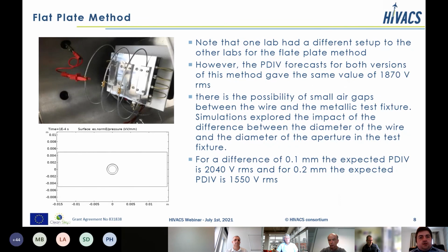So one of the labs had a slightly different test setup for the flat plate. So the geometry was considered in the models in this case. For the other labs, we estimate that the PDIV for the flat plate method is 1870 volts RMS. But with this specialized test setup, there's also the possibility of small air gaps. Now, we don't know exactly what the size of those air gaps is, so it's very difficult to make an exact estimation of the PDIV. So looking at the sort of sensitivity, we see if we have a 0.1 millimeter gap, we get 2040 volts RMS, and then it falls considerably as that gap gets bigger.